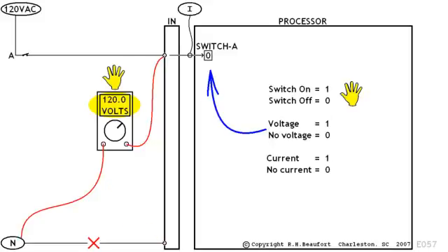Setting up the meter like this can lead to some incorrect conclusions, unless you really stay on your toes. It's fairly common practice for a technician to clip one of the voltmeter leads to a known neutral connection and then move the other probe from one point to another while looking for voltage. Quite a few technicians have been tricked by this setup. Their line of reasoning usually goes like this. Okay, I've got a good voltage signal coming into the module, so the switch and the wiring must be okay, but the bit still won't change to a 1, so the input module must be bad.